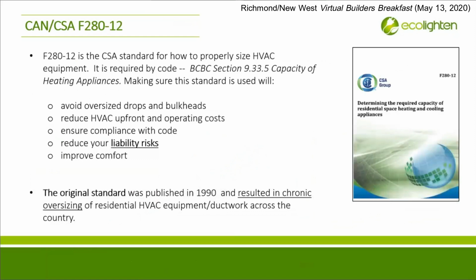CSA F280-12 is just the accepted method of applying the math and physics to determine how much heat loss and heat gain will occur in any given building. It's the most current and most accurate methodology, and it's required by code, although not yet strictly enforced in most jurisdictions in BC. Throughout Canada and the US, there have been multiple independent studies that have confirmed what many of us already knew, that far too many systems are grossly oversized. This means equipment gets bigger, ducting is bigger, budgets are bigger, operating costs are higher, life cycle of equipment is shorter, comfort is compromised, and the risk of liability goes up.